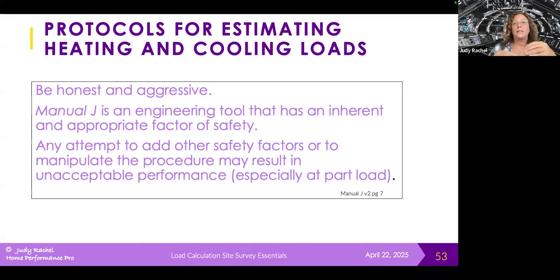So right there, the number of times that sensible heat equation is used throughout the entire load calculation procedure is continually giving us a little bit more and a little bit more of what we're going to call a safety factor, so you're not going to have to worry that your output is going to make you end up undersizing the equipment. The other place where we end up with a safety factor is when I said things like the procedures tell you that you can round up to the nearest foot, or to the nearest half foot, depending on which part of the structure you are measuring. That is also an additional safety factor that ends up giving us a load calculation that very safely predicts the heating and cooling loads, and we don't have to worry that when we are honest and aggressive with our measurements and our description of the assemblies, we're ever going to end up with an undersized piece of equipment based on the heating and cooling loads that this load calculation procedure puts out.